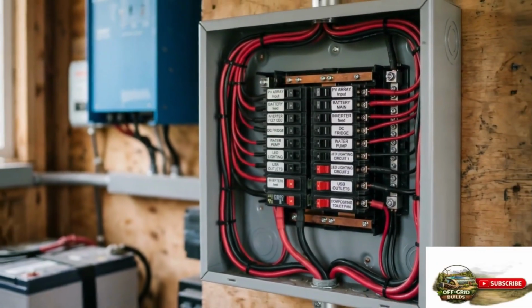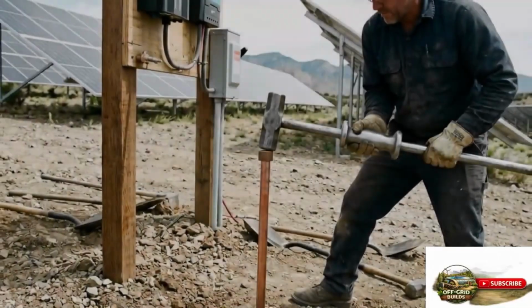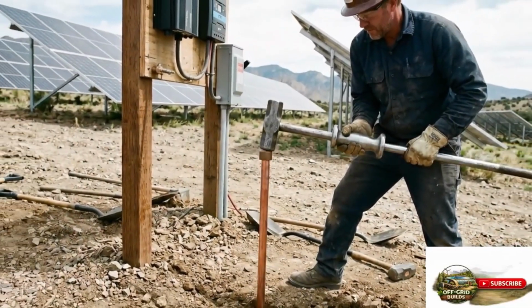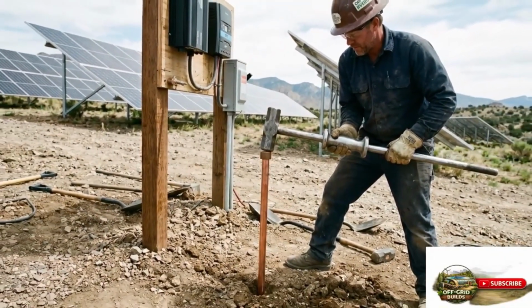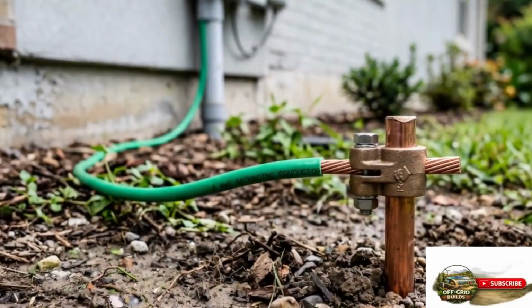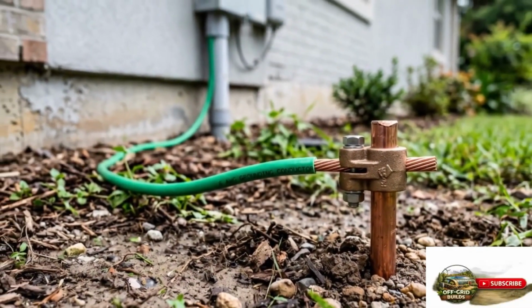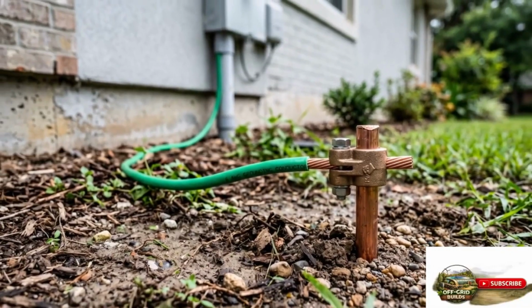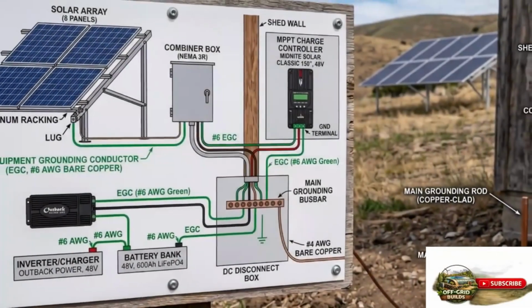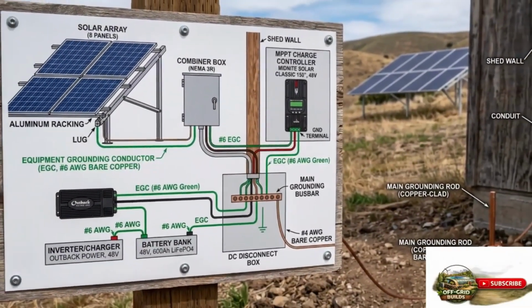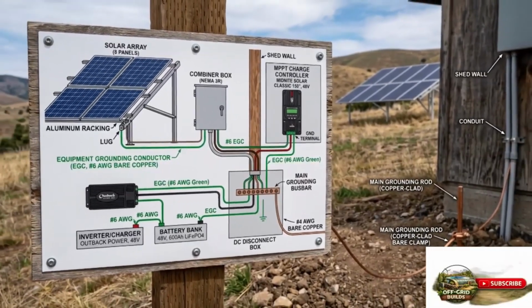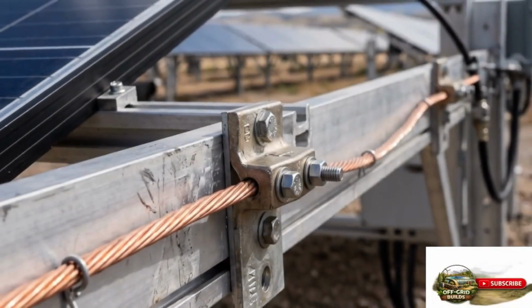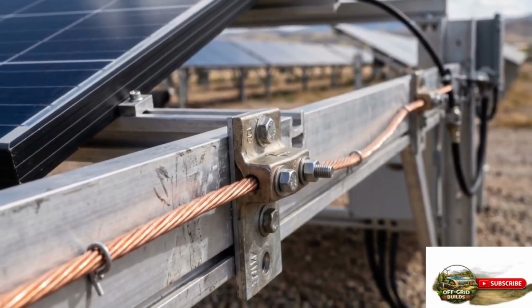Grounding your system correctly. Grounding is the aspect of solar system installation that beginners most commonly underestimate and that creates the most serious safety risks when done incorrectly. A properly grounded off-grid solar system protects personnel from electric shock in fault conditions, protects equipment from lightning-induced surges, and is required by the National Electrical Code for permitted installations.